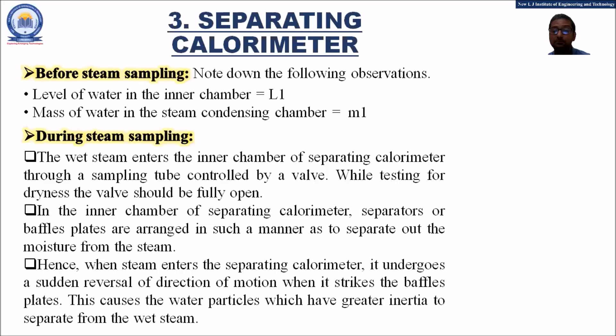Hence now, when the steam enters the separating calorimeter, it suddenly undergoes a reversal of direction of motion when it strikes the baffle plates, as we have already seen in the arrows provided in the experimental setup figure. This causes the water particles, which have the greater inertia, to separate from the wet steam. Moving further, because of the inertia, the water particles move downwards and are collected at the bottom portion of the inner chamber of the separating calorimeter.